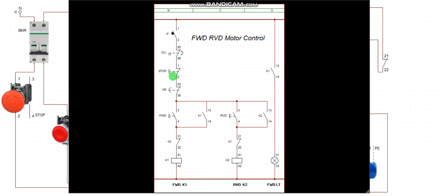Then whenever I see the stop button, I showed you the 3D, it's going to be terminal 1, terminal 2. That is for close contact. If you are using open contact, it's going to be terminal 3 and terminal 4. So this one is our voltage monitor terminal. This one does not have a specific terminal depending on the product.